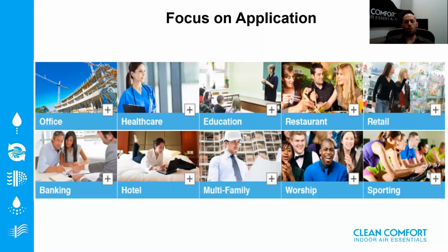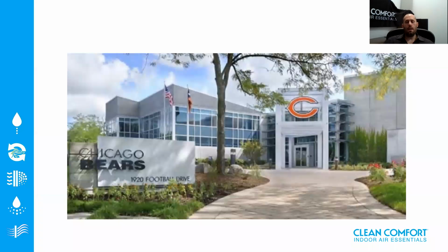Let's take a look at a few different applications. This was a football training and office center. Now, usually we get these calls to look at the fitness area or maybe the locker rooms, but this call was about the office smelling like hamburger. The cafeteria exhaust was really close to the rooftop unit for the office. So here we added some purifiers to that rooftop unit and knocked out the hamburger smell.